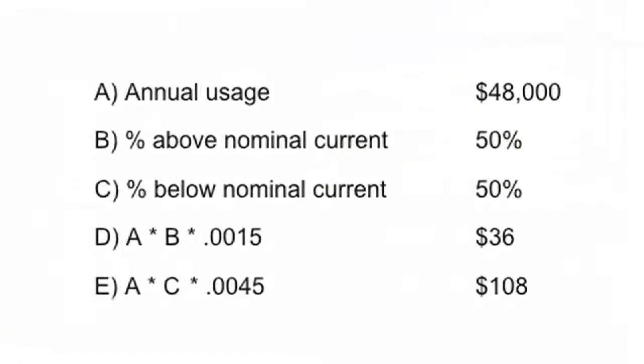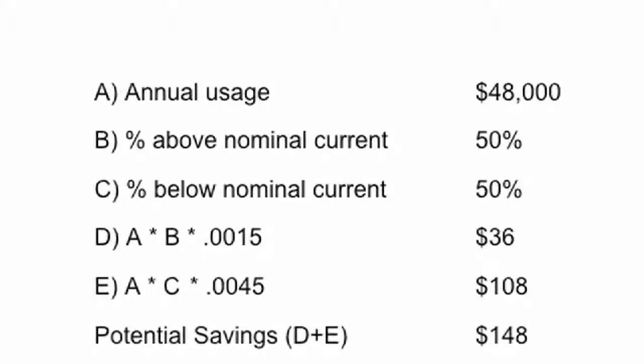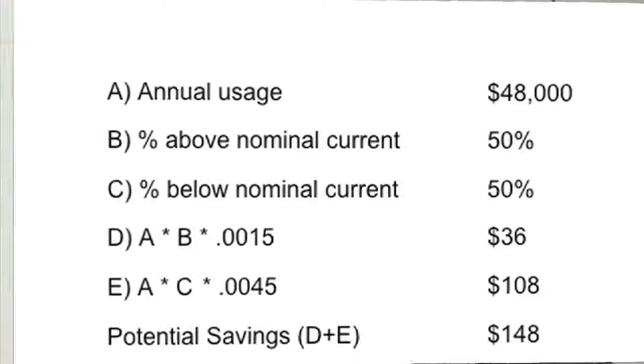So potential savings for a utility on an installation like this with say about a $48,000 a year electric bill could be $148. You say, well, that's not a whole lot. Okay? Why would I really kind of change anything that I'm doing now for $148? Well, the difference in price from a regular CT to a highly accurate CT is about $25. You see that would pay for itself in about 2 months' time. You say, well, I'll save $125.